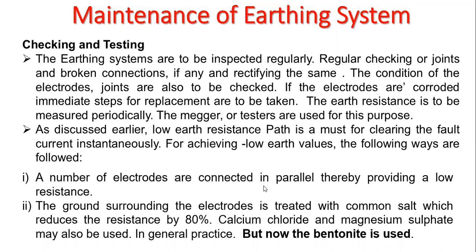A number of electrodes are connected in parallel, thereby providing a low resistance path. That means we can simply connect a number of electrodes in parallel in order to reduce the resistance. Or secondly, the ground surrounding the electrode is treated with common salt, which reduces the resistance by 80%. That means the ground surrounding the electrode, where the electrode is placed, that area should be treated with common salt, so that the resistance will be reduced by 80%, or calcium chloride or magnesium sulfate can be used in order to reduce the resistance. But nowadays, in general practice, bentonite is used in order to reduce the earthing resistance, or in order to provide a low earth resistance path.